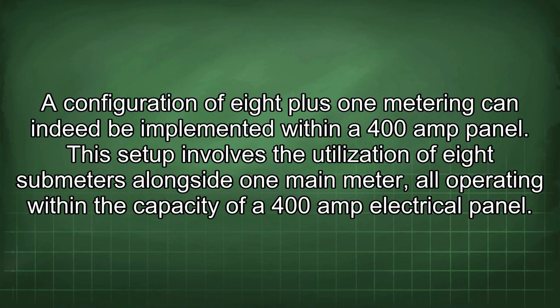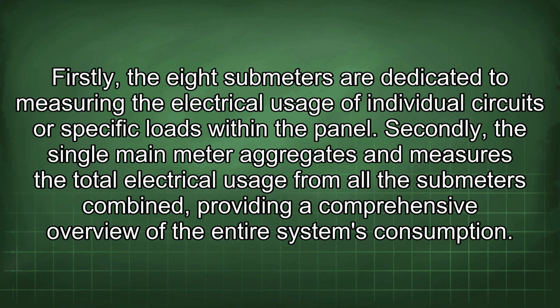A configuration of 8+1 metering can indeed be implemented within a 400 amp panel. This setup involves the utilization of 8 submeters alongside one main meter, all operating within the capacity of a 400 amp electrical panel. Firstly, the 8 submeters are dedicated to measuring the electrical usage of individual circuits or specific loads within the panel. Secondly, the single main meter aggregates and measures the total electrical usage from all the submeters combined, providing a comprehensive overview of the entire system's consumption.